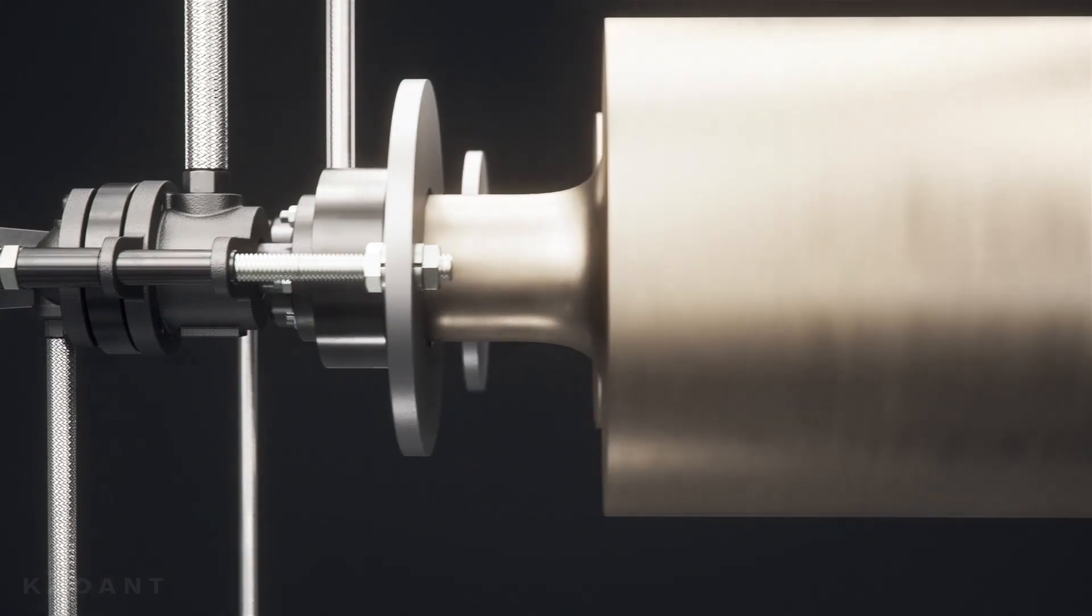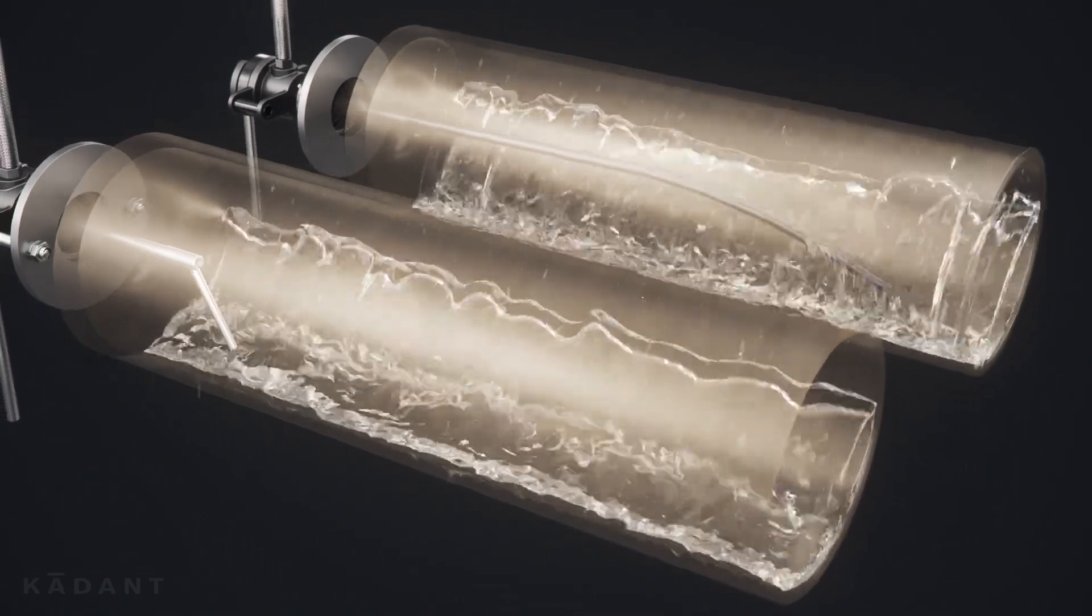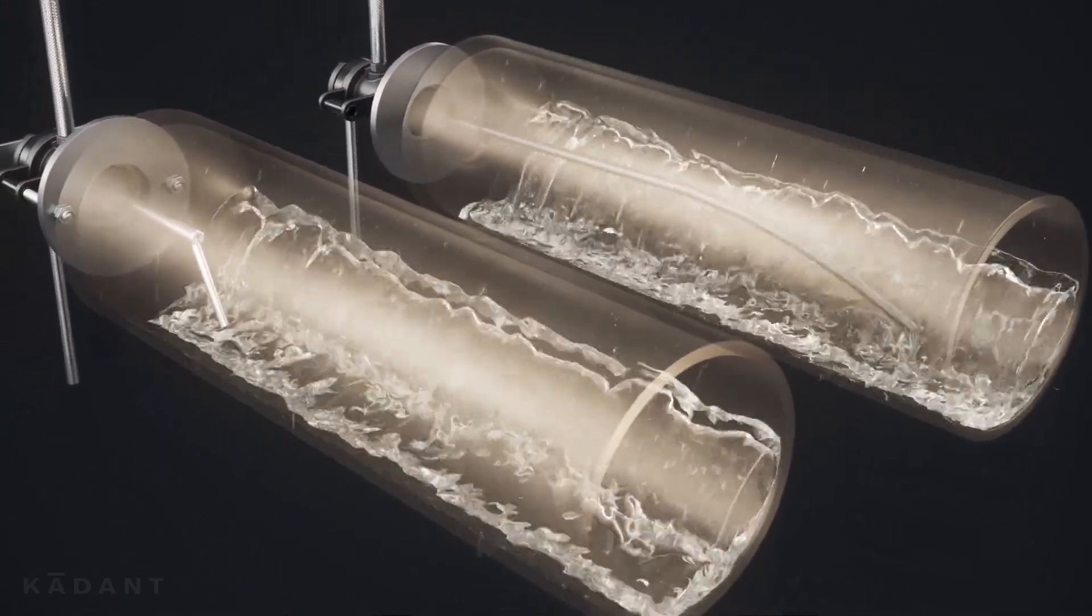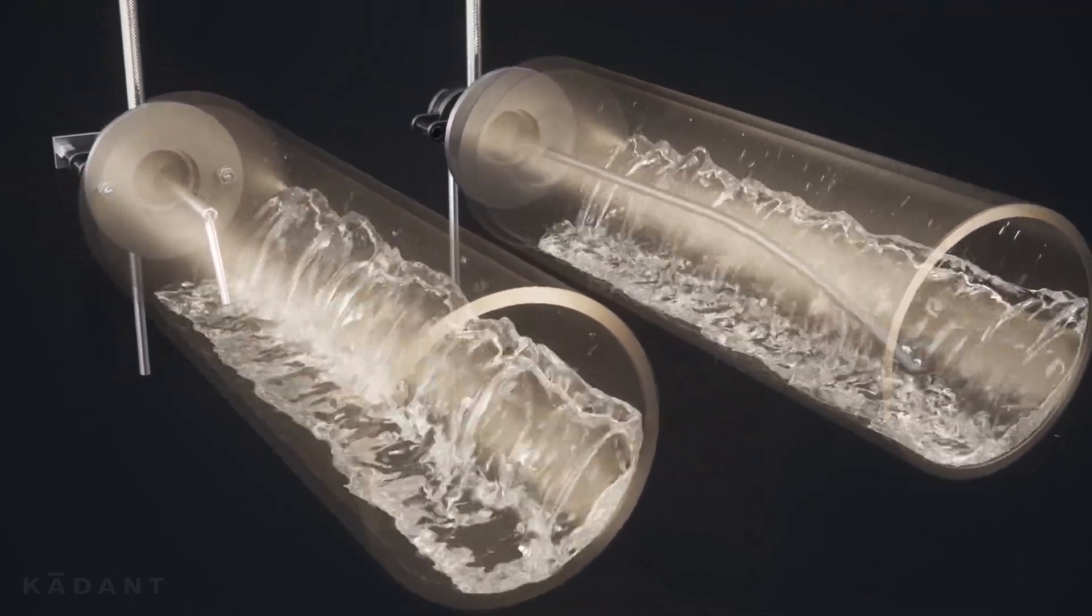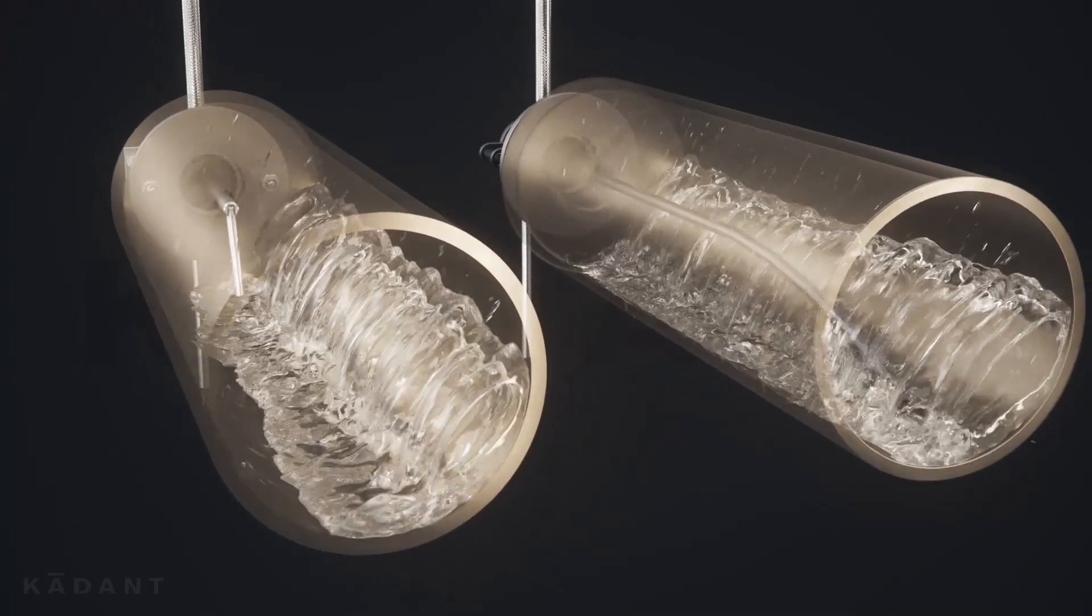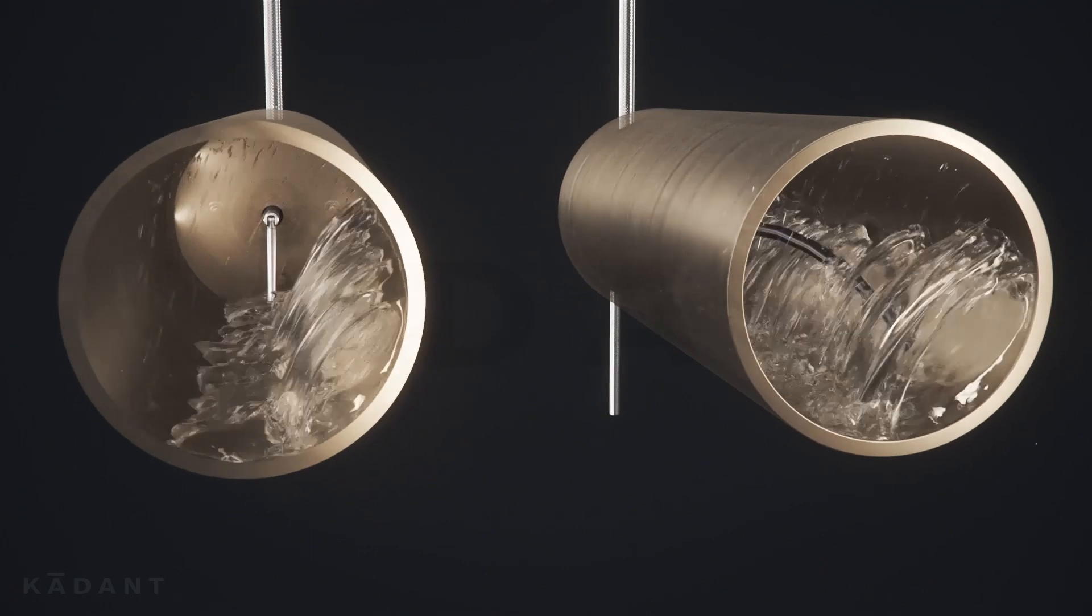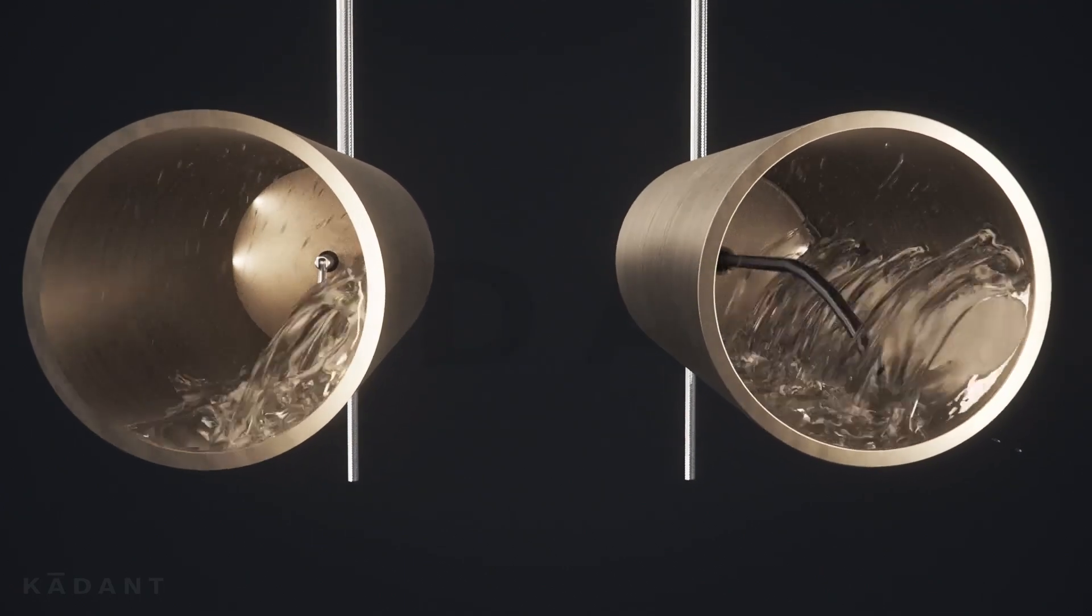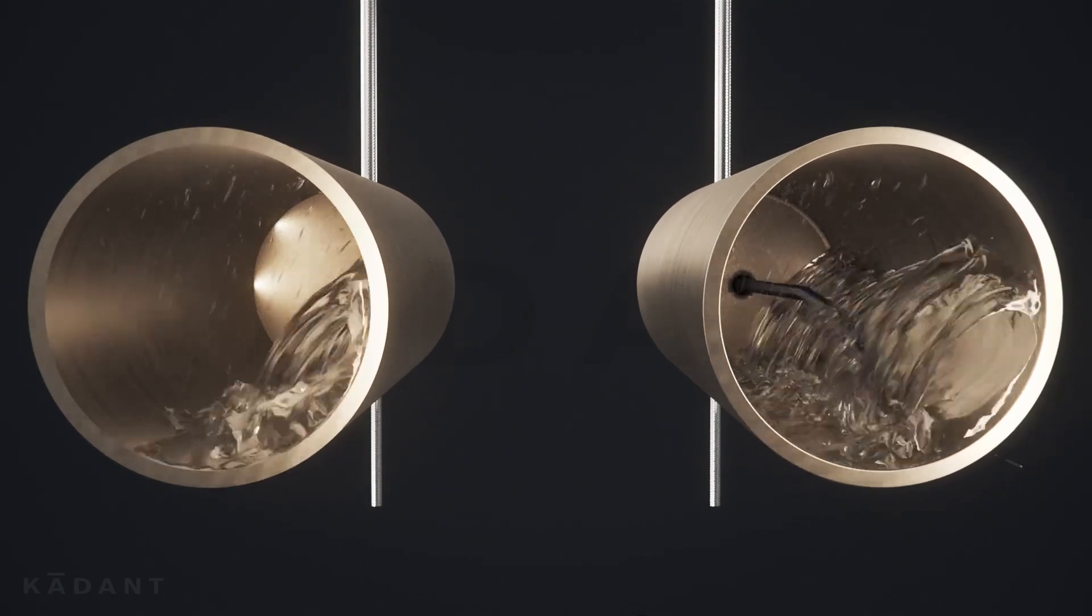The LJX rotary joint and rigid siphon system provide a more robust solution than bent siphon pipe systems. Bent pipes are gradually curved to fit through the roll journal and are three times the length of the LJX rotary joint rigid siphon. Bent siphon pipes move erratically and provide inconsistent condensate removal. The result of a bent pipe system is inefficient and uneven heat transfer and eventual metal fatigue failure.